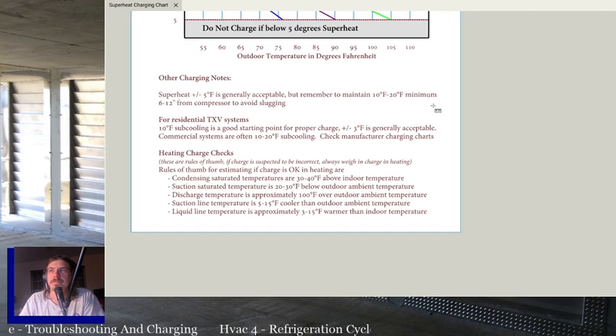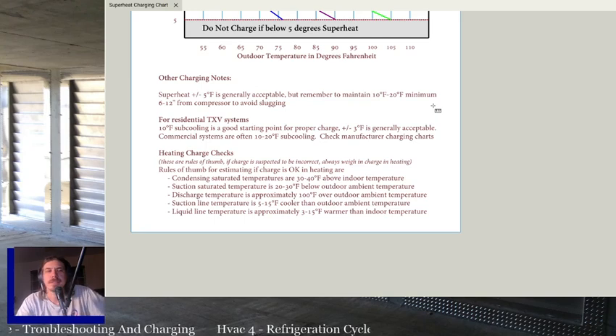TXVs are a lot more common, TXVs and EEVs these days. For residential TXV systems, I'm sure you guys know, but it doesn't hurt repeating it. 10 degrees subcooling is generally fine. Just start out at 10 degrees subcooling. Systems used to be like 7. I'd see some that were 7 and some that were 9 and some that were 12. I think most of the ones I've put in for the last couple years have always just said 10. 10 degrees subcooling is usually fine. Plus or minus 3 is generally fine.